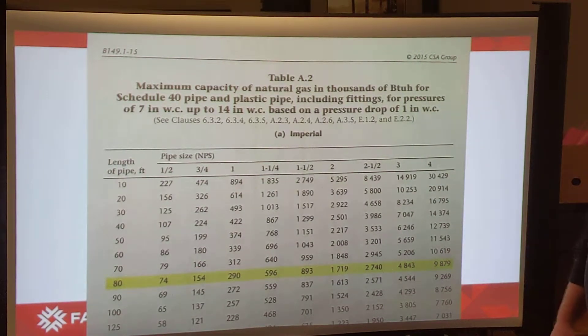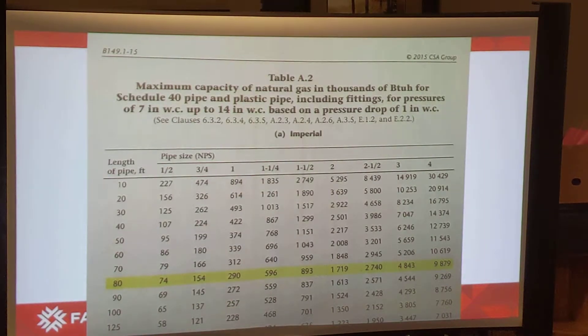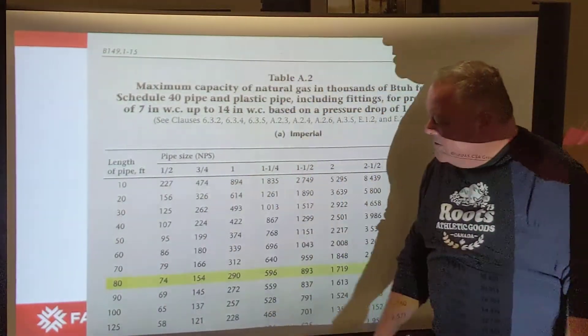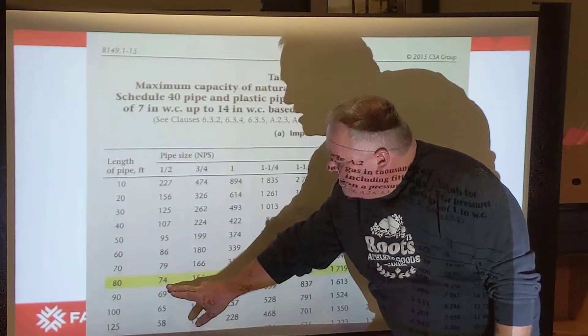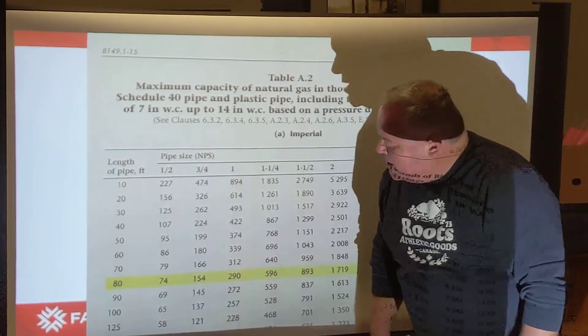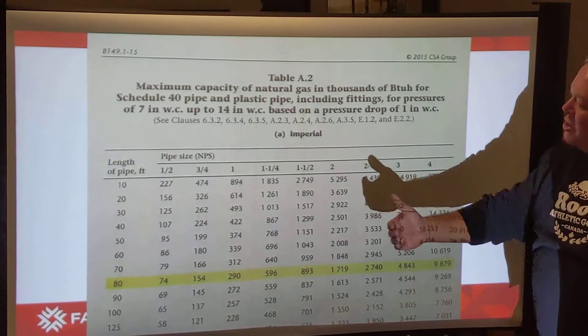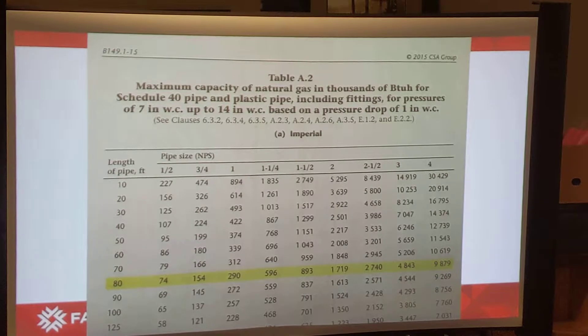The actual table is on page 118 of your B149.1-15 codebook. I've highlighted the 80-foot pipe length section. At the 80-foot code zone, we move across until we find a number of 375 or larger — 596 is the first value larger than 375. Going to the top of that column, we see inch-and-a-quarter is the pipe diameter. Half inch handles 74,000 BTUs, three-quarter handles 154, one inch handles 290, and inch-and-a-quarter handles 596, so we use inch-and-a-quarter for the entire schedule 40 section.